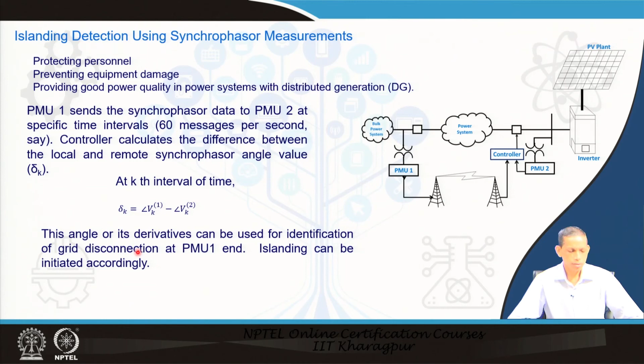So, for that reason you can say that islanding detection becomes an essential one, and in that case the local islanding detection schemes can be useful, and if that fails also, if the PMU data are available, it can supplement that either at the high voltage side or in the distribution system also. For that, the angle between the two voltages, this side and that side, is indicative in case of islanded systems. If this breaker is open, the angle drifts independently between these two, there is no synchronism between them, and therefore it will drift, you can say, in the forward or backward direction. So, that angle is indicative of the corresponding situation. In the normal situation, when the grid is connected, this delta angle becomes smaller, and it will consistently be close to the steady state value. So, this corresponding angle is indicative of the islanding situation, and its derivative or double derivative can be faithfully used for such detection.